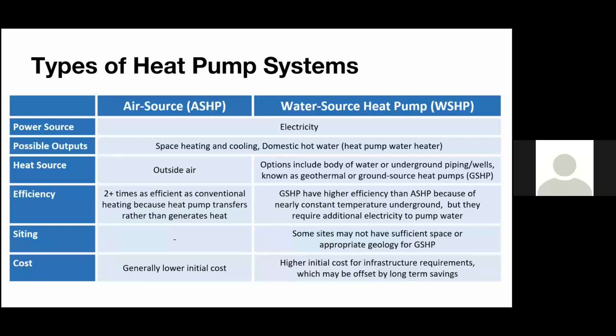But the other way we use water source heat pumps is with that condenser water loop, we then try to dump that heat or get that heat from somewhere else, like the ground or a lake, and that's where your geothermal water source heat pumps come in. Those tend to be called ground source heat pumps as well. It doesn't need to be in the ground. They can be in a lake, but it is a ground source heat pump. It stands for heat pumps that are meant and rated for geothermal temperature ranges. Some manufacturers have one model of water source heat pumps you can use for both geothermal and standard water source. Some manufacturers have a specific line of water source heat pumps that they call ground source heat pumps that are meant for geothermal applications.